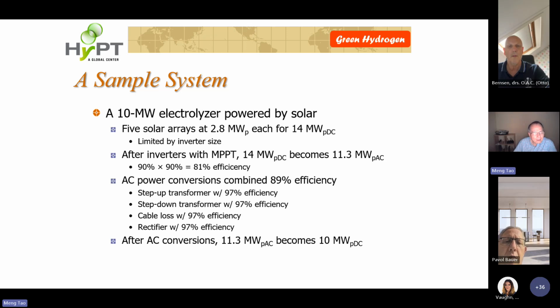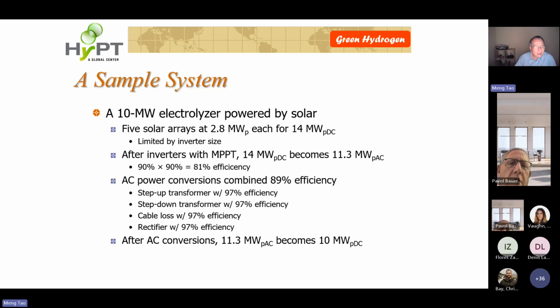A 10 megawatt electrolyzer powered by solar. If we do AC coupling long distance, we need a 14 megawatt solar system. And then we need 5 solar arrays, each at 2.8 megawatts peak to add up to 14 megawatts total. The reason is that the size of the inverter is limited. You will not be able to find a 14 megawatt inverter, and 3 megawatt is probably as large as you get today. So that's why we need 5 solar arrays.